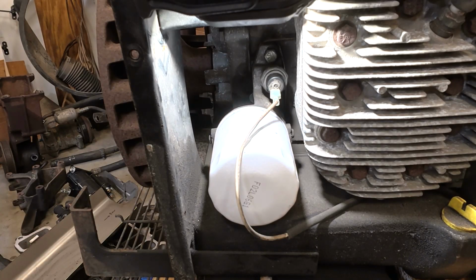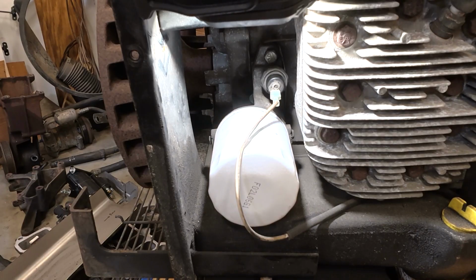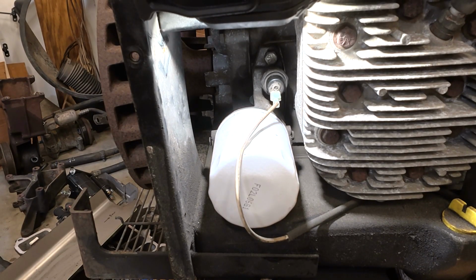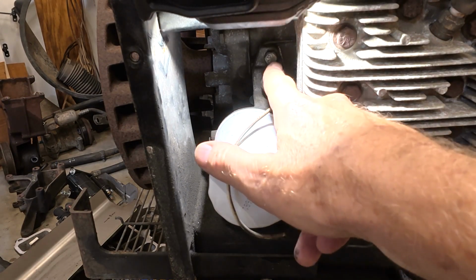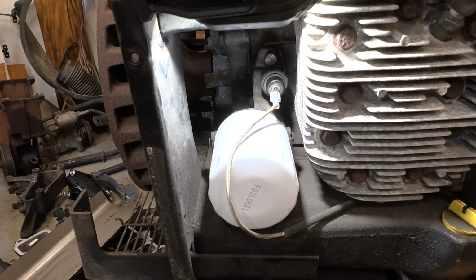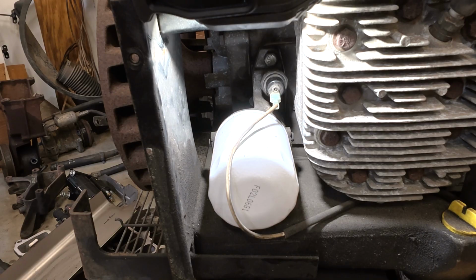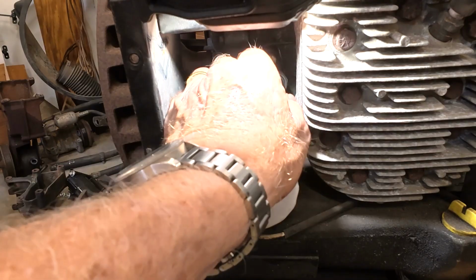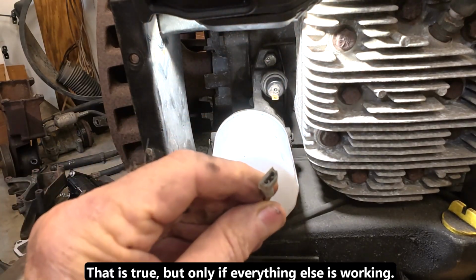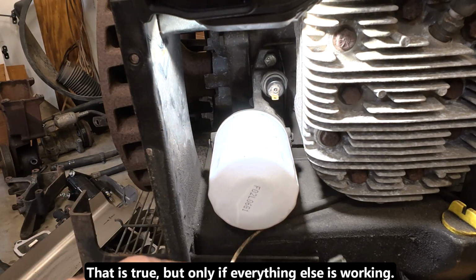When these generators start up, as soon as you release the start button, they stop. It can mean the oil pressure sensor isn't working. The main control board on the generator tests whether there's oil pressure, and if there isn't, it won't let the engine continue once you start it. So it lets you start it so it can develop oil pressure, but if it doesn't sense any, it stops the engine. I'd read a couple of things and seen a couple of videos where they say you just unplug it and put this directly to the ground to bypass it, but that didn't do any good for me, so I decided to replace it.